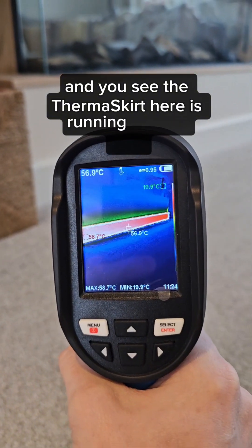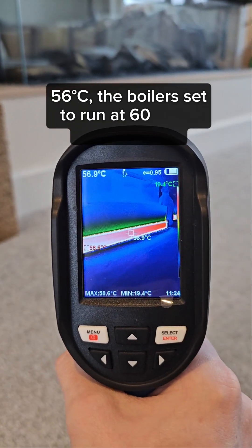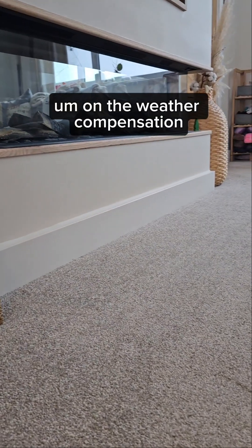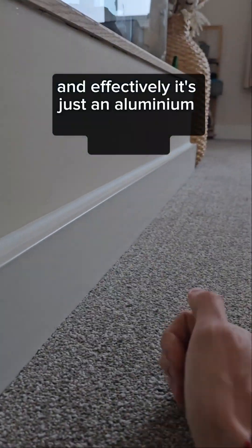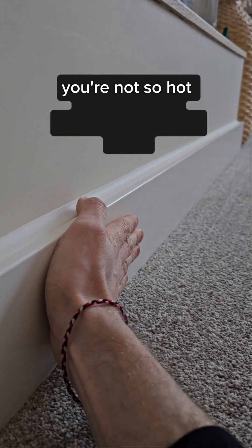You can see the ThermaSkirt here is running around 57-56°C. The boiler is set to run at 60°C when it's minus 3 outside, on weather compensation. That's the ThermaSkirt there — it's effectively just an aluminium panel that's hot to the touch, not so hot you can burn yourself, but toasty warm. It runs all the way around the outside of the room and that makes it warm.